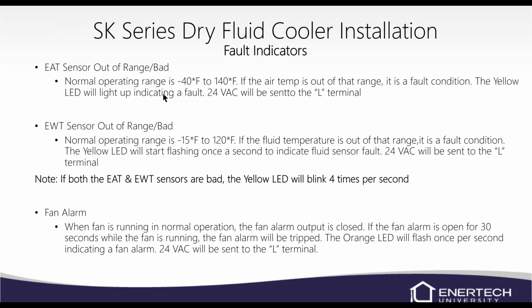The fault indicators, again, you have entering air temperature sensor out of range. The normal range is -40 to 140. If it is out of range, the yellow LED light will blink, indicating the fault. And there will be a 24-volt signal sent to the L terminal or the lockout terminal. So if you've got that going back to your heat pump and then to your thermostat, then it'll let the thermostat know that there's an issue.